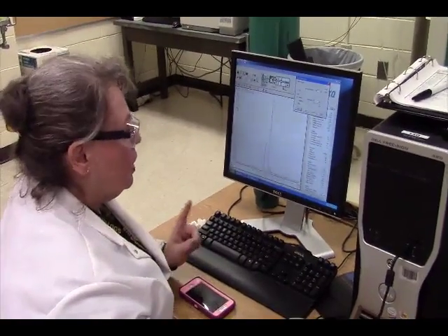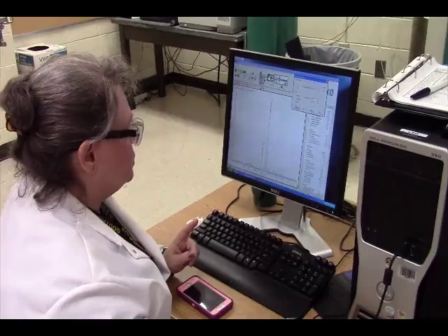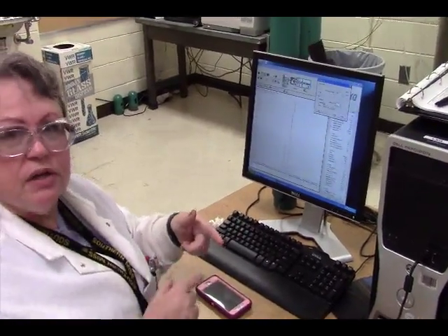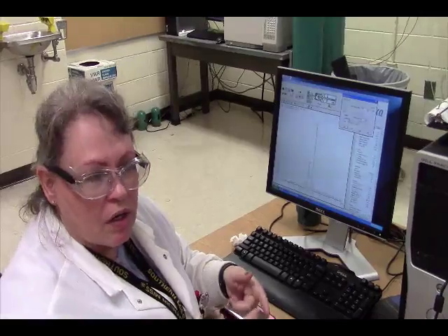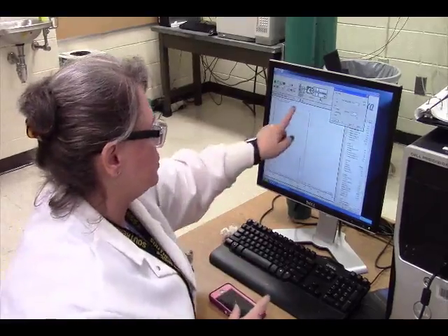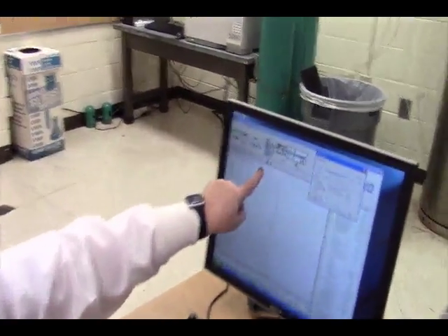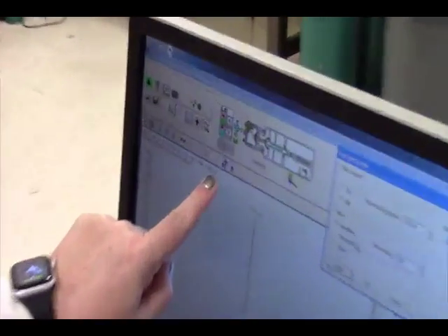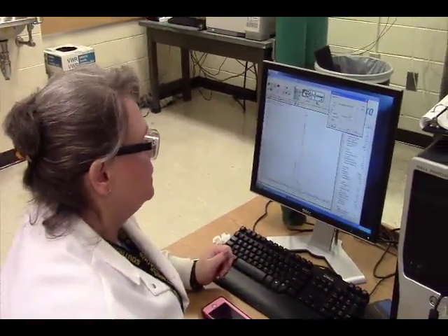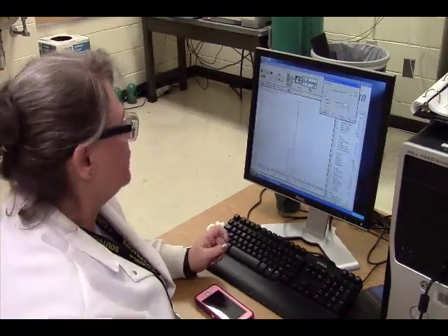Now we should be finished with LXQ. What we do need to know how to do, we got to wash the instrument. So what we're going to do is we're going to take methanol water or methanol THF and then acetonitrile and clean our instrument to make sure that this is between 10 to the second, 10 to the third. Ignore that now because it's not running. I'm not actively putting a flow through the instrument right now because my syringe pump is off.